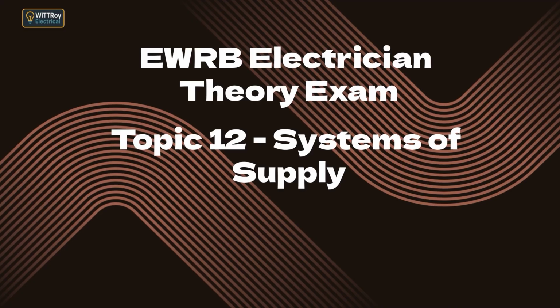12.2 Multiple Earth Neutral, MEN, System. 12.2a. Explain how the MEN system is configured. The MEN system connects the neutral conductor to the installation's earth bar using a solid MEN link. The neutral is also earthed at the distribution transformer. The earth bar is connected to an earth electrode. This creates multiple connection points between the neutral and true earth. The system ensures the neutral stays close to earth potential and provides a low resistance path for fault current, allowing protective devices to disconnect quickly.